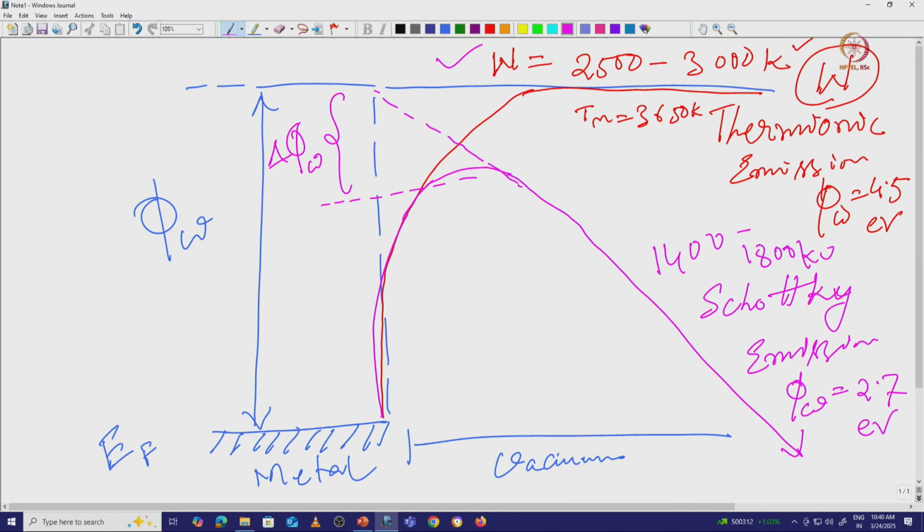The good thing is that when you use this much energy, you are not very close to the melting temperature of the filament, so you are not damaging it. And the beam will be much more coherent if you are not using very strong heat energy.